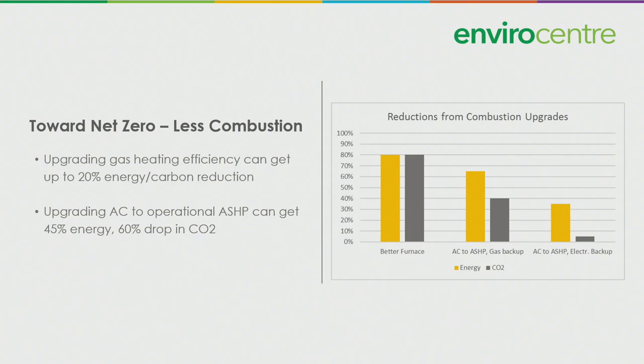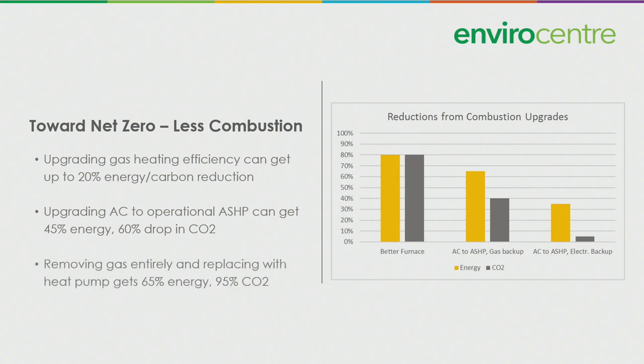And in the third scenario here, we remove the gas entirely and replace it with a heat pump with electric backup. And that gets you 65% reduction in energy and a 95% reduction in your CO2. So these are much more economical upgrades and much more feasible than doing the envelope upgrades, which take a lot of planning, a lot of time, a lot of materials, and they take time to install as well.